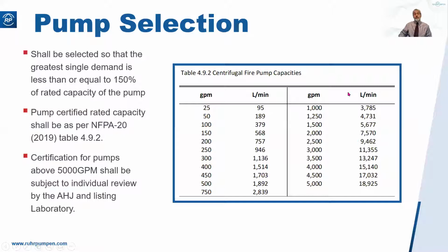So NFPA-20 specifies the capacities, 25, 50, 100, etc., going through up to 5,000 gallons a minute at various pressures, generally in the region of 100 to 150 psi. We can go higher, but on a case-by-case basis, and there are quite a few out there that are around 7,500 gallons a minute. Among standard pumps, it's 5,000 gallons a minute top.